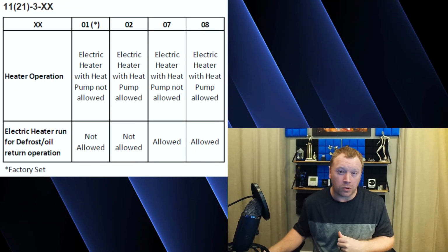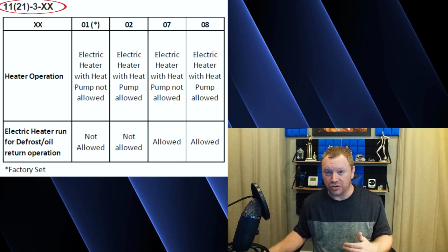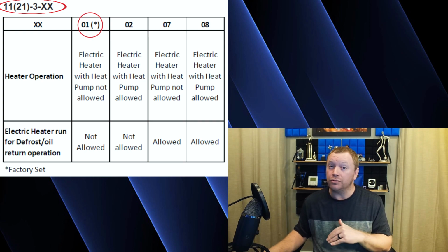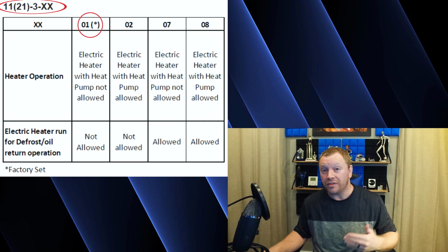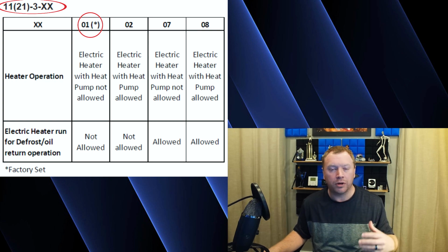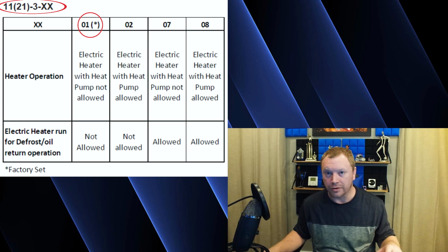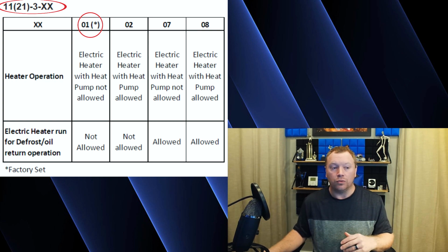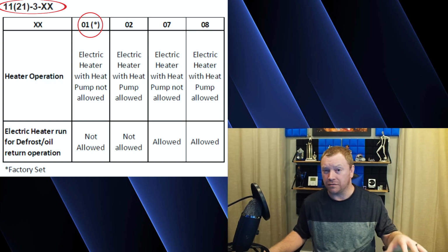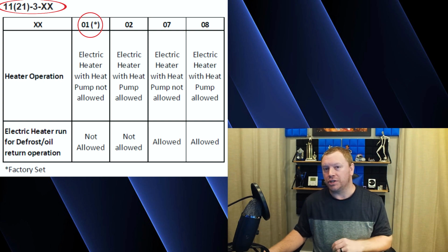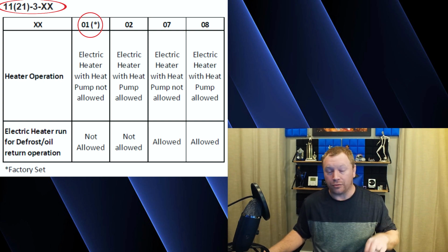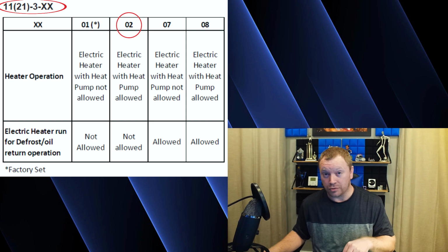Those settings are going to be mode 21, 3-01, which is the default. If you do not want the strip heat to run with the heat pump for supplemental purposes to help the heat pump catch up should it fall behind for any reason, and you also don't want it to run during defrost. If you want it to run with the heat pump, that is allowed, but you still don't want it to run during defrost because defrost is only 6 minutes, then you would change mode 21, setting 3-01 to 3-02.